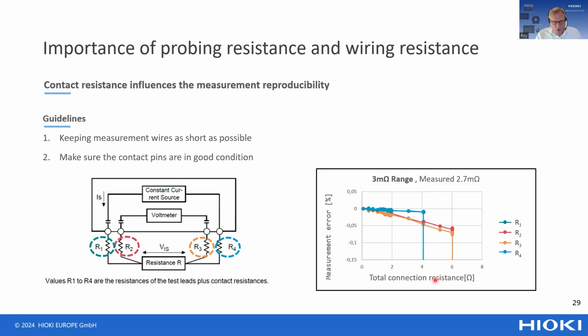Further, this also shows that there is a limit to the resistance that the connection can have, because otherwise the measurement instrument is not able to generate the current that you want to have for the low resistance measurement. So if the circuit for the source is exceeding 4 ohms in this case, then it's not possible to do any measurements any longer.